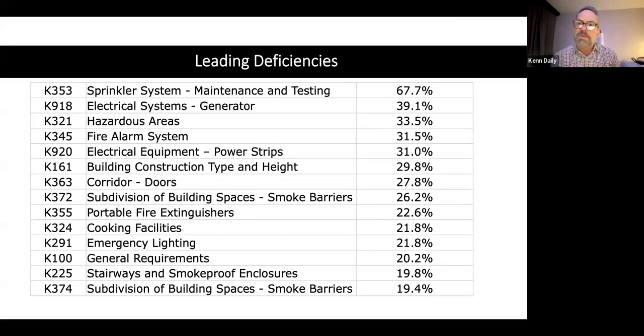And then hazardous areas, and primarily the issue is going to be where you either had an illegal hold open device on a magnetic hold open door or an automatic closer door, where you use a wedge or a coat hanger or duct tape or some crazy thing, or that you have so much COVID or infection control storage like masks and gowns and such that you shove it in a former patient room and you don't have an automatic closure on the door. So it's an inappropriate storage room, which is really common across the country right now because so many of us have so much infection control stuff stored, and there's no place to store it. So then we put it in a room. We don't think about turning that room into a storage area.